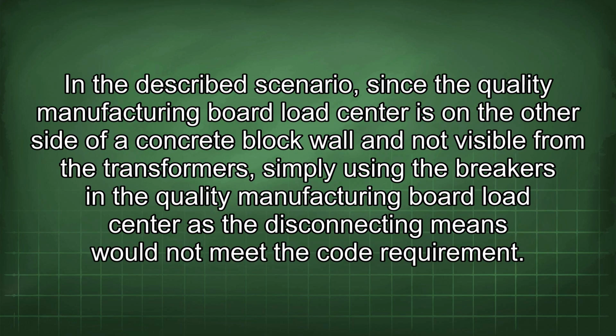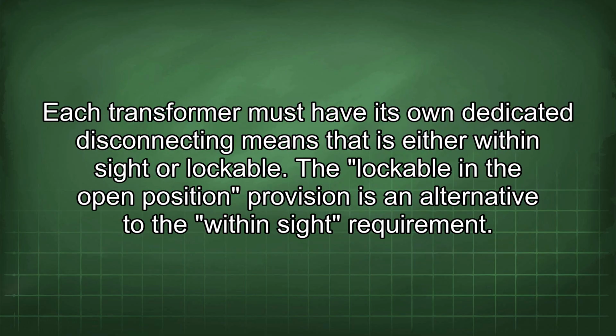In the described scenario, since the Quality Manufacturing Board load center is on the other side of a concrete block wall and not visible from the transformers, simply using the breakers in the Quality Manufacturing Board load center as the disconnecting means would not meet the code requirement. Each transformer must have its own dedicated disconnecting means that is either within sight or lockable. The lockable in the open position provision is an alternative to the within sight requirement.